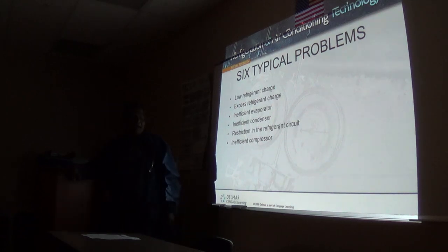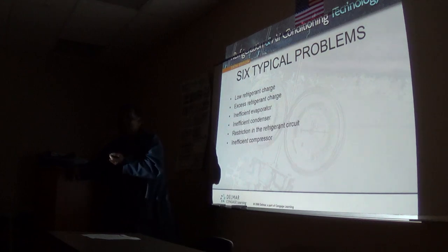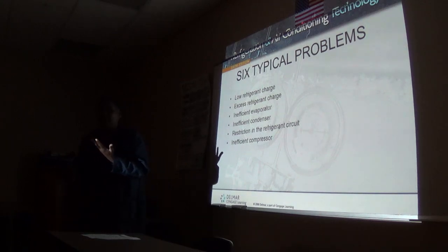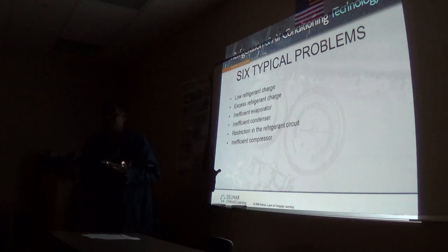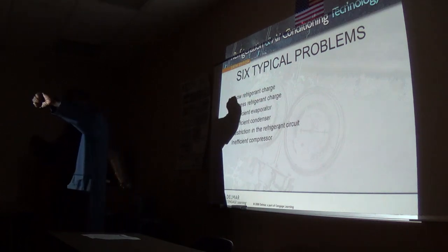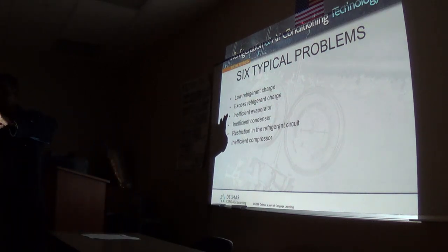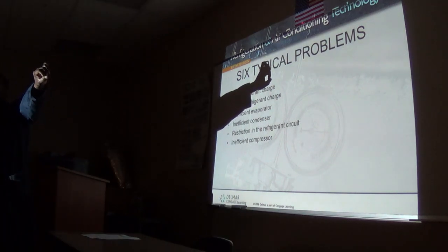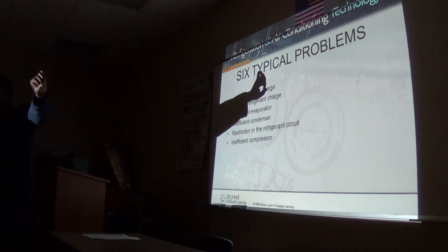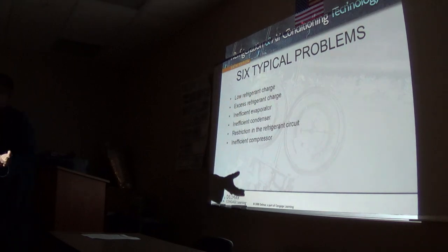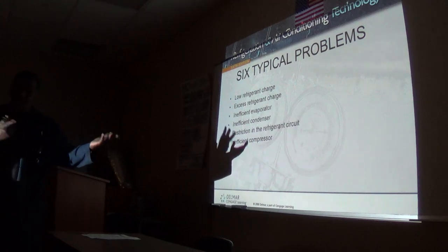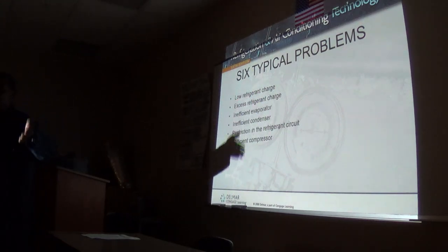134A has a tendency to, remember I mentioned earlier that these blends of refrigerant are about some of the best detergent mankind ever made. It washes all the crap that was in those lines and takes it straight to the capillary tube. First it's going to go through the filter. So if enough small particles pass the filter, it's going to go to the cap tube. In some cases, the filter will block up before the cap tube does. The filter takes everything out, fine, you will have a blockage there or you can have it in the capillary tube.